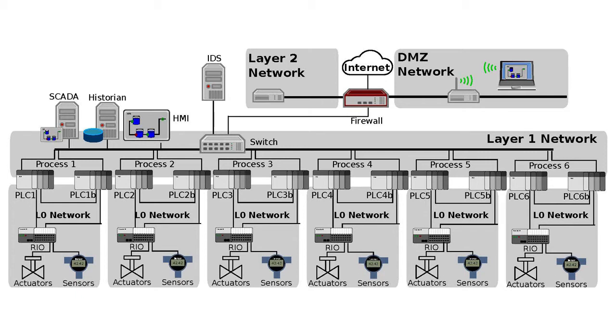In both the Level 1 and the Level 0 network, the industrial EtherNet/IP protocol is used for communication. This industrial protocol is in particular used by Allen Bradley products. Although the name is EtherNet/IP, it's not directly related to Ethernet or IP. Instead, it's running on top of TCP — it's an application layer protocol that allows exchange of measured sensor data, sending commands to actuators, reconfiguring the logic of the PLCs, updating firmwares, and similar more complex actions on the network. The Level 1 network contains the SCADA workstation, the historian, and also the HMI. These will periodically query all the PLCs for current sensor data and also send new control actions if required.